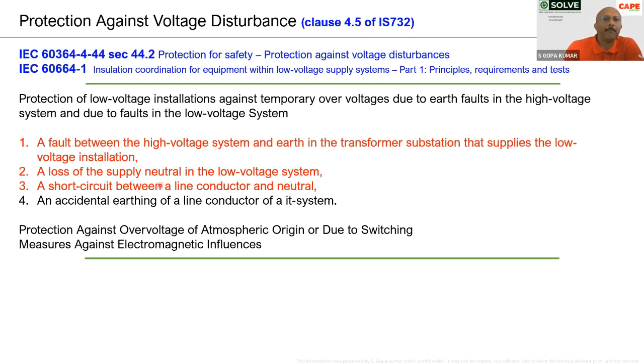This means a short circuit between line conductor and neutral. This means there is a problem in one of the circuits, and that particular circuit tripped. But parallelly, an accident can happen in the parallel circuit, because the parallel circuit is stressed with more voltage for a longer duration. If the disconnection time is more, then we are actually in trouble.